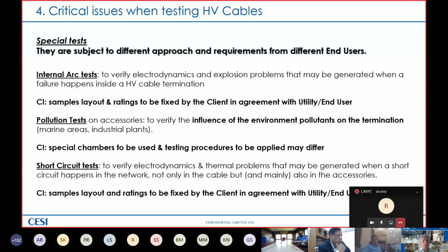Talking about critical issues during a special test. Of course, we must say that in this case, there are different approaches and requirements from different end users. Internal arc tests are used to verify electrodynamics and explosion problems that can be generated when a failure happens inside a high voltage cable termination. In this case, there are layout and ratings that have to be fixed by the client in agreement with the final end user. Pollution tests on accessories are used to verify the influence of environmental pollutants on the termination, as I said, marine, desert areas, or industrial plants. Also in this case, the special chambers and testing procedures that are applied may differ.